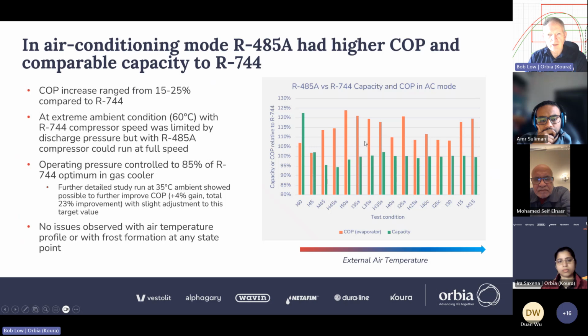So in air conditioning mode, what we found was actually better than we'd first expected from thermodynamic modeling, but we're comfortable with the results, having gone through the analysis in detail. And what we found was that across the board in air conditioning mode, we had a COP gain that ranged between 15% compared to CO2 up to 25%.